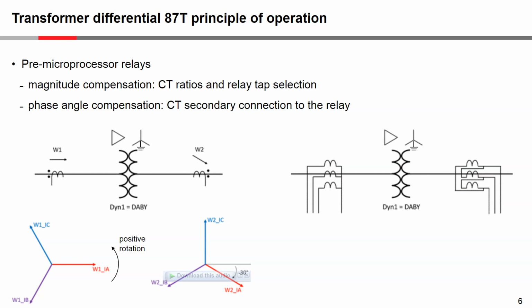So if we look at this example where I have a DYN1 or a DABY, depending, I guess, on which side of the Atlantic you are, how you would reference the transformer connection. But in this particular case, you can see that it's a delta Y transformer, and the current on the winding 2 side lags the current on the winding 1 side by 30 degrees.